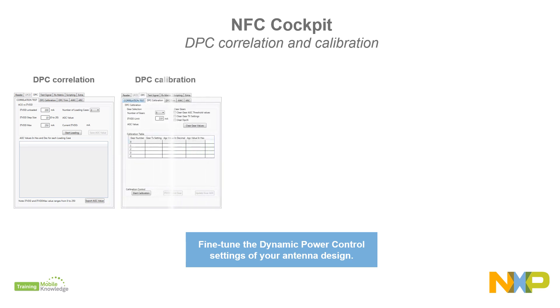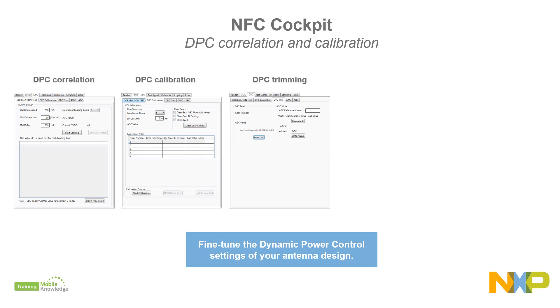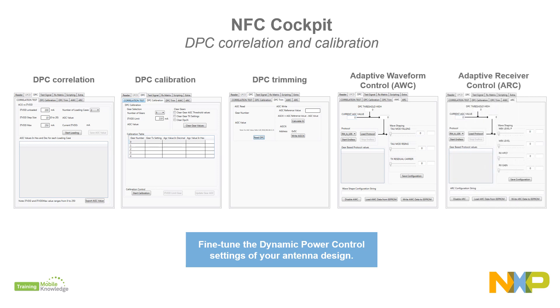This UI supports the entire process, starting from the DPC correlation test with different types of loads, the DPC calibration to control the field strength according to the loading conditions, the DPC trimming to compensate production tolerances between devices, the adaptive waveform control to optimize the transmitter pulse shapes, and the adaptive receiver control to optimize the receiver settings.